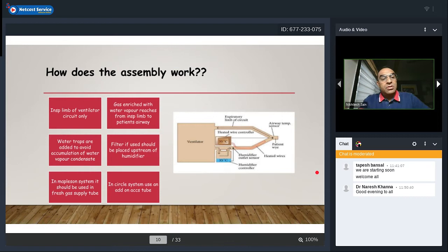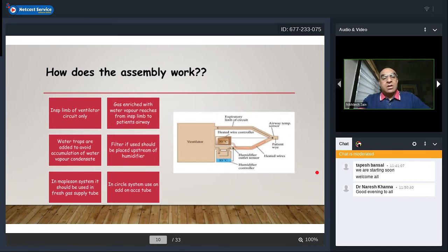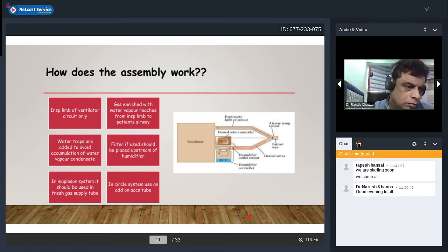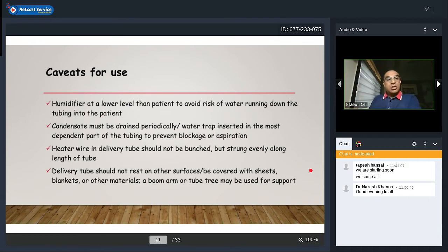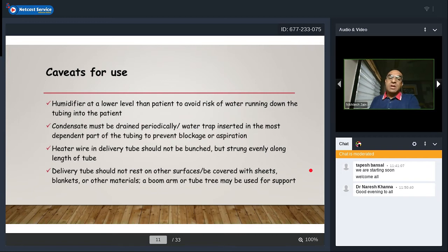The assembly is placed on the inspiratory limb of the ventilator circuit only. Gas enriched with water vapor travels from the inspiratory limb to the patient's airway. Water traps are added to avoid accumulation of condensate. If using a filter, it should be placed upstream of the humidifier. The humidifier should be at a lower level than the patient to avoid the risk of water running down the tubing. Water vapor condensate must be drained periodically, with a water trap inserted at the most dependent part of the tubing.